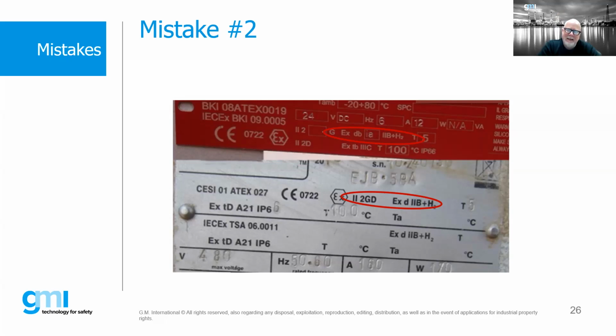So there's a difference between these labels, right? This is two different manufacturers, and they're basically making a flame-proof box. So when we look at the top one, we see EXDB, and then we see IA, and then gas group, T code, and so forth. Down here, we see EXD. Now, D is not bad, meaning the markings. There's actually a new requirement to put a letter at the end of the protection concept that is a fairly new development. So now things that were previously marked EXD will now be marked DB. That doesn't mean that this bottom one is not good. That's not the case. That's just the older markings.